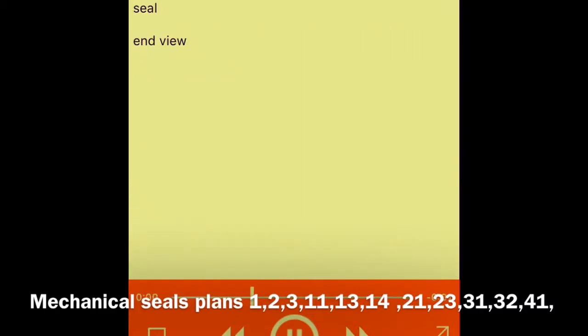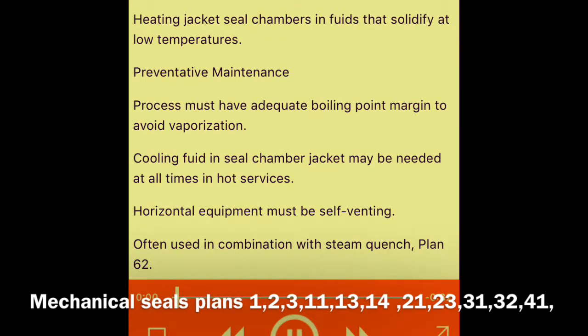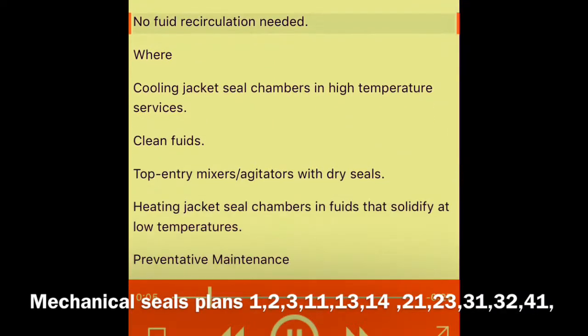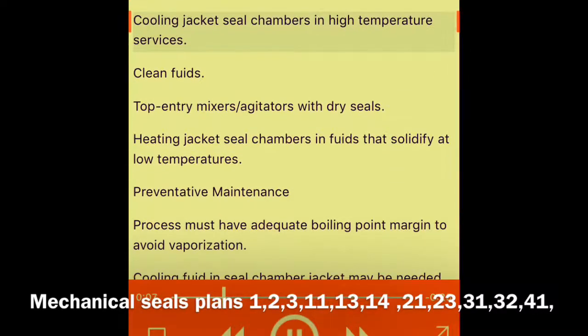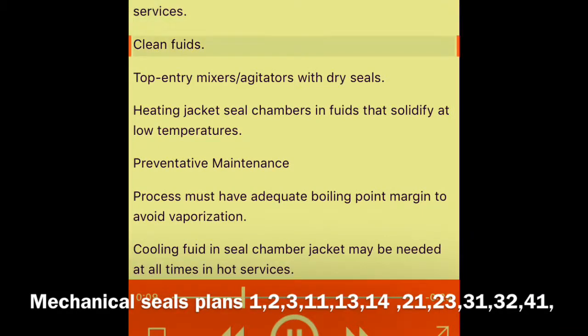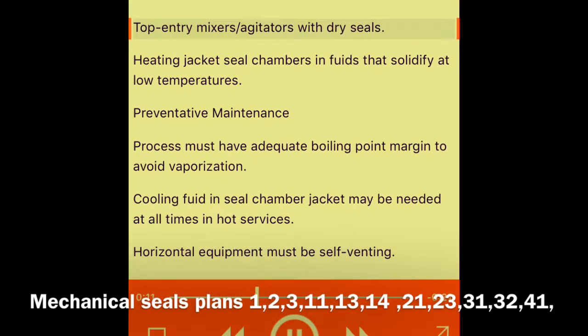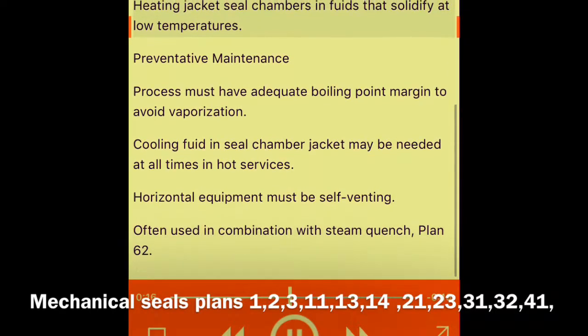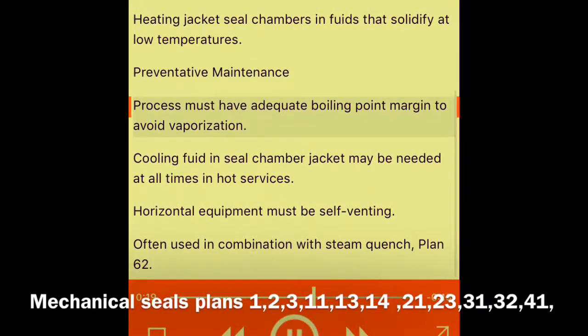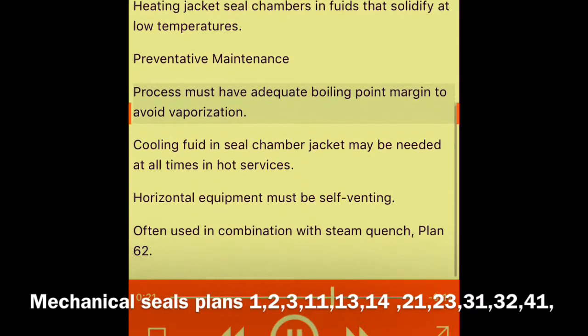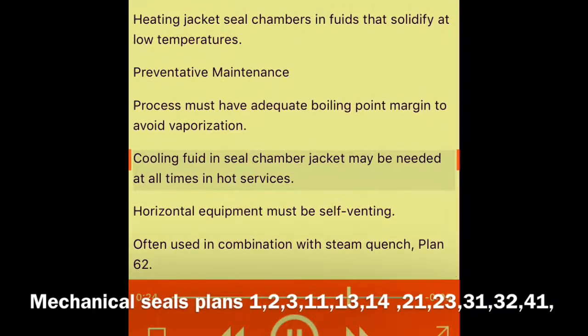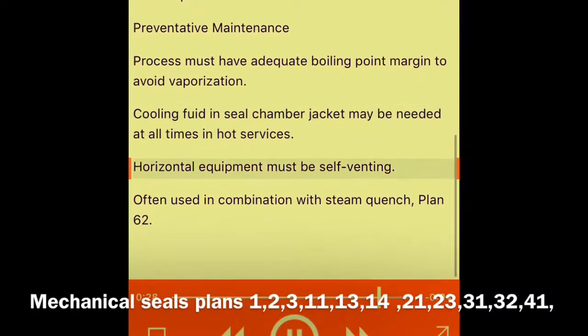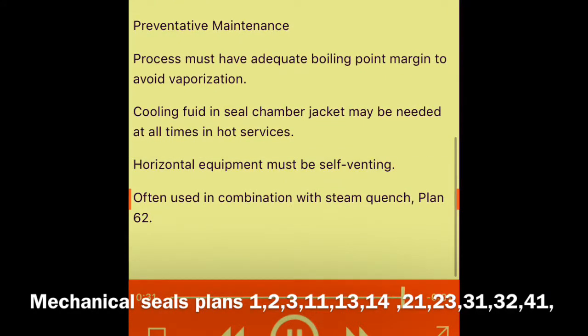Plan 02 — seal end view. What: dead-ended seal chamber with no flush. Why: no fluid recirculation needed. Where: cooling jacket seal chambers and high temperature services; clean fluids; top-entry mixers and agitators with dry seals; heating jacket seal chambers and fluids that solidify at low temperatures. Preventative maintenance: process must have adequate boiling point margin to avoid vaporization; cooling fluid and seal chamber jacket may be needed at all times in hot services; horizontal equipment must be self-venting. Often used in combination with steam quench Plan 62.